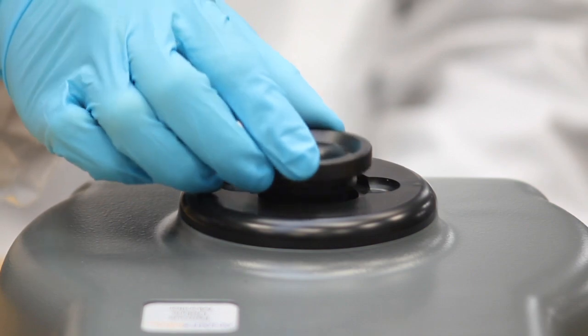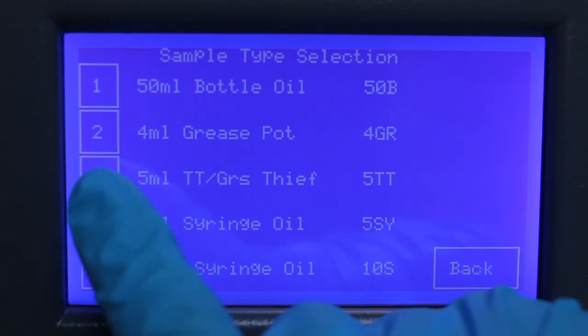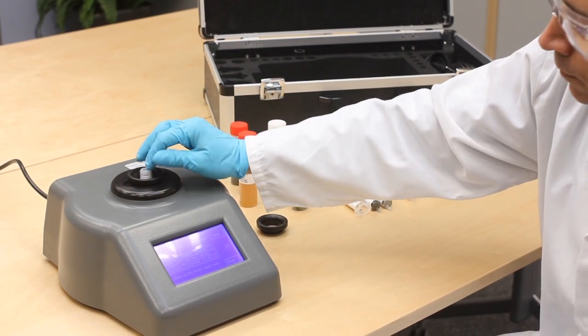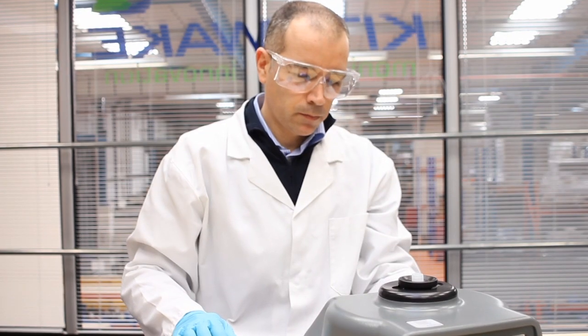The FDM Plus measures uncombined ferrous wear debris in samples taken from a variety of machinery types. Unlike laboratory methods of atomic absorption or spectroscopy, it's not affected by particle size.